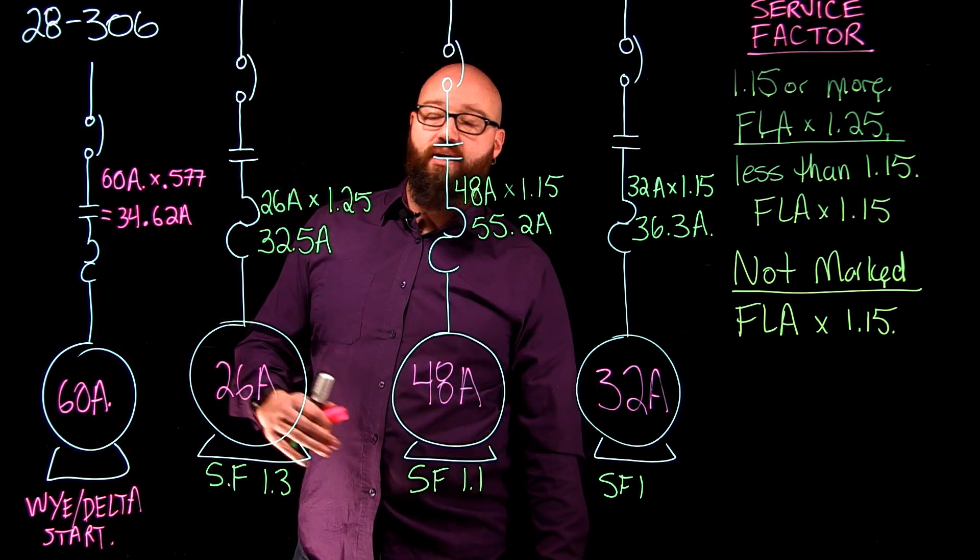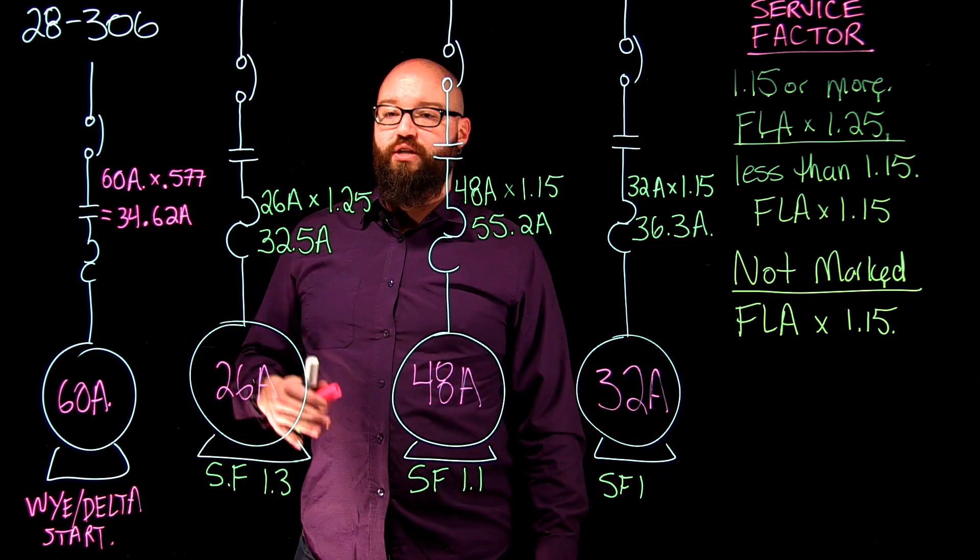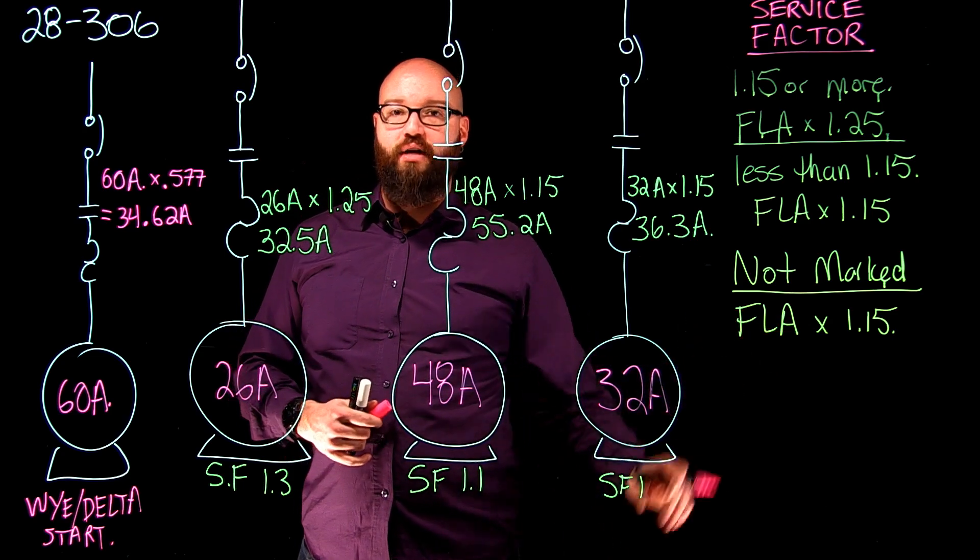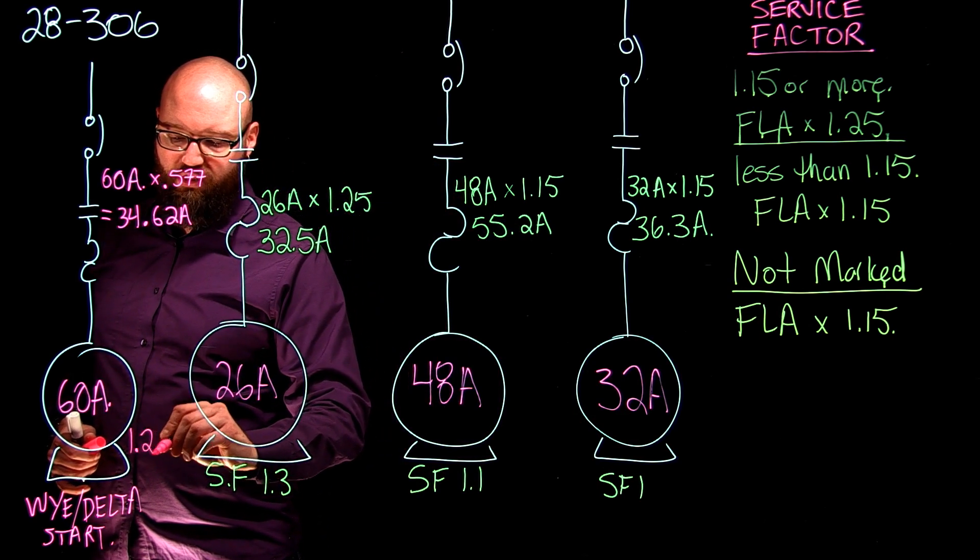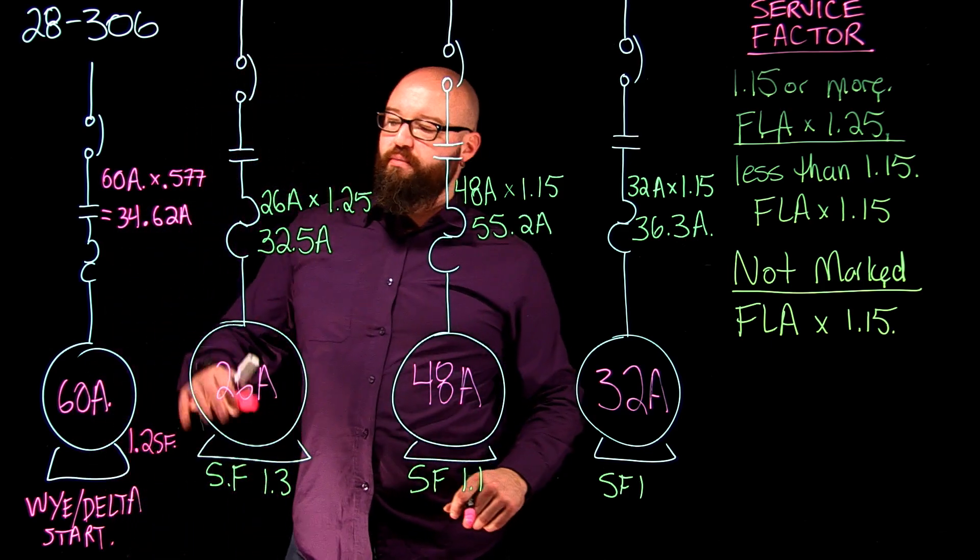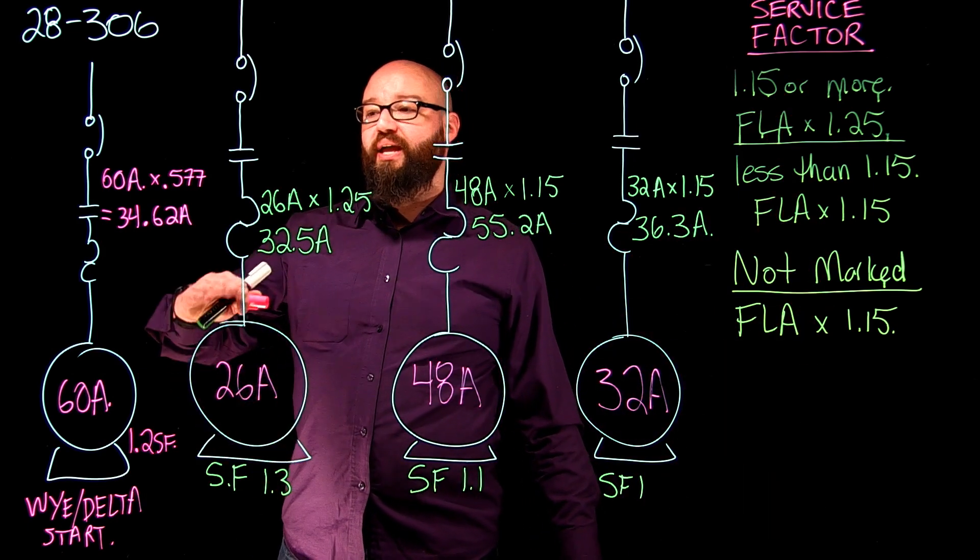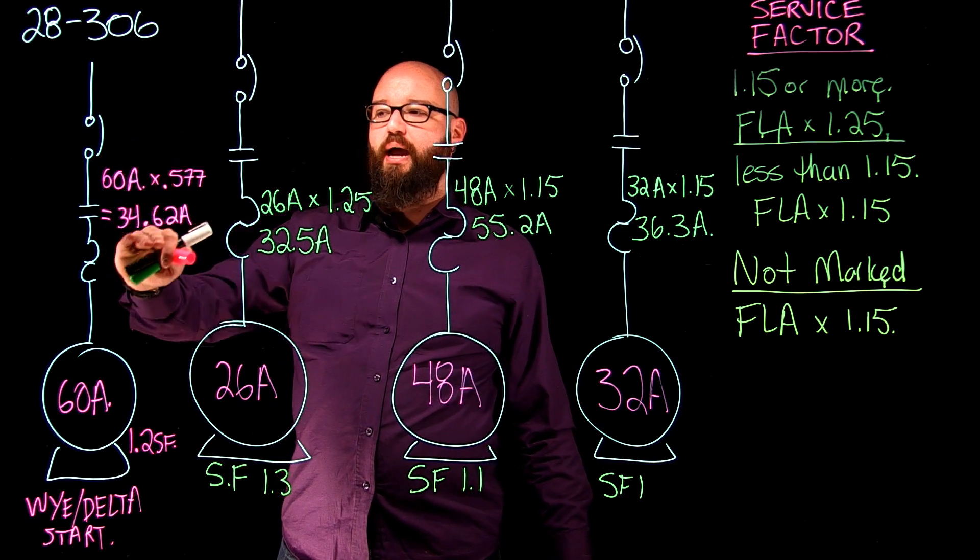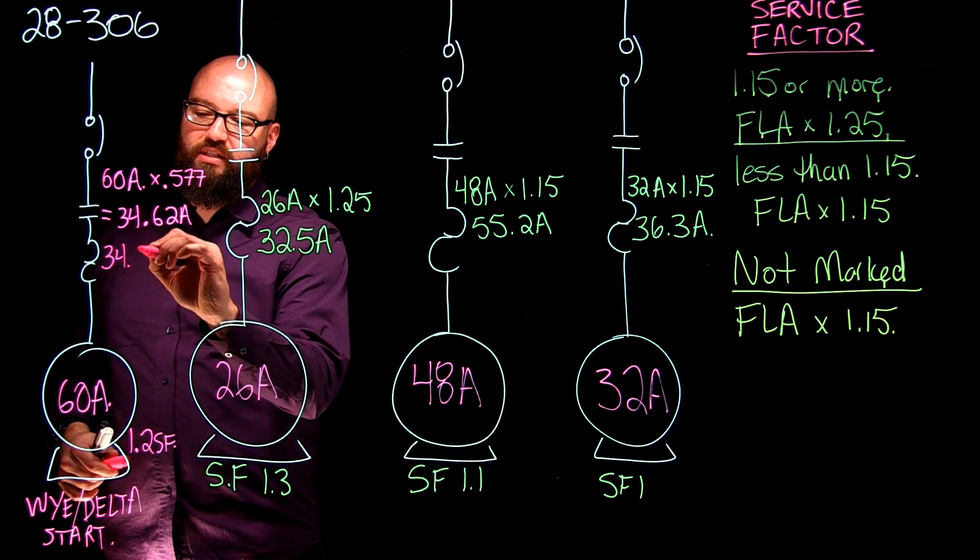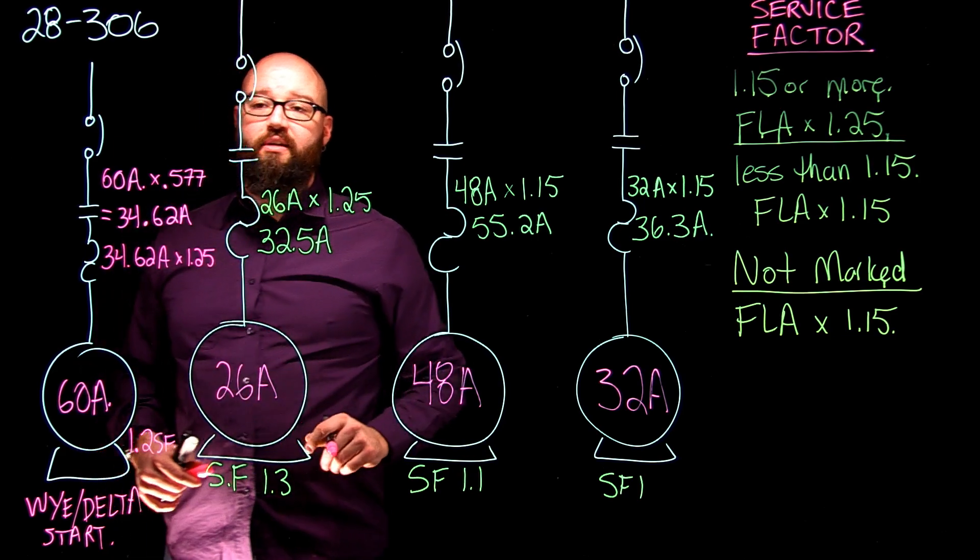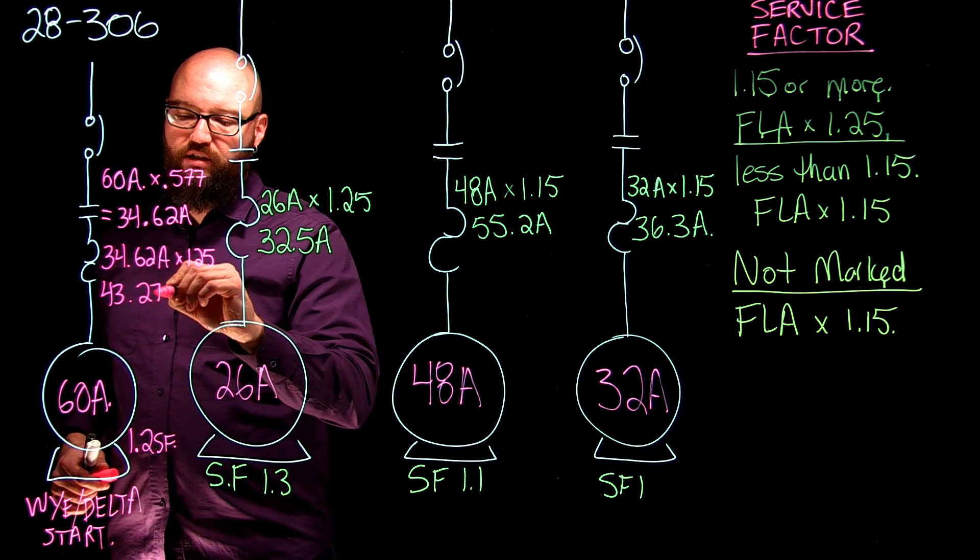Now we're not done yet, because that's just the phase current value. Now I can apply what I know from over here, which is if I have a service factor marked, and we're going to throw a service factor on this one, we're going to say this has a service factor of 1.2. If my motor had a service factor of 1.2, I would apply my 125% because it's over the 1.15. But again, I'm going to use this phase current that I calculated here, not my line current of 60 amps but my 34.62 phase current. So we're going to take our 34.62 amps and multiply it by 1.25, and again that's going to give me my maximum overload setting of 43.275 amps.